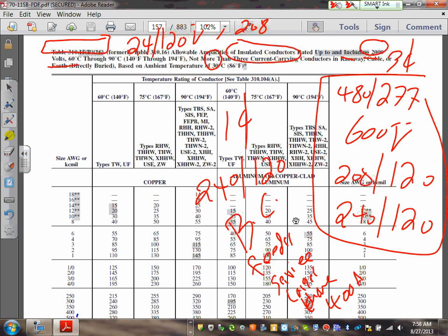The table that we've just covered is the baby table. Up to 400, you use it. The residential 240/120, higher than 400, you must come here. So that's why this is the table that you need to know. Any comments about this table, guys? I want to remind you, it's for three conductors in a conduit or in a cable. The ambient temperature is 30.